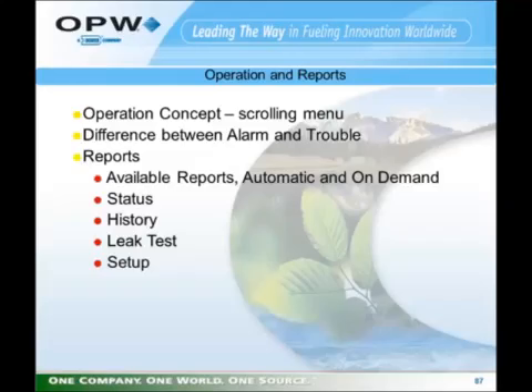The difference between an alarm and a trouble: a trouble means that the system has detected an operational difficulty with a device or circuit of the system. It is unable to operate properly, so it is going to generate a trouble alarm to point to the device or circuit that's giving the issue. An alarm is an actual alarm condition, whether it be a leak, a high product, a low product, or something like that. What an alarm means is that the system is functioning properly. It has detected a condition that exceeds one of the settings that you have programmed into the system.